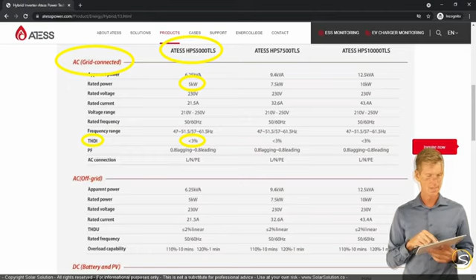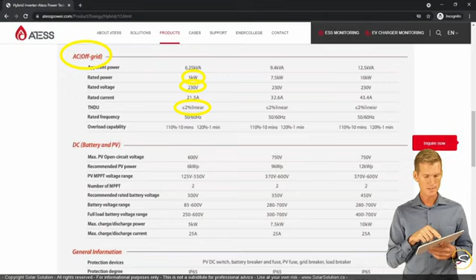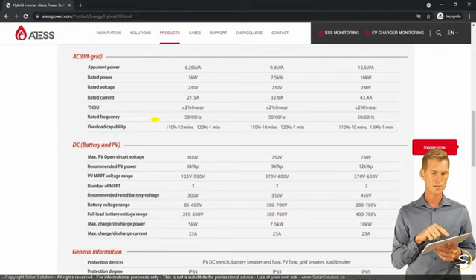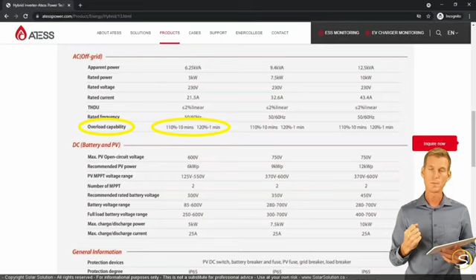And here in the second section you can see the values for when you're running off grid, so that's the connection between the hybrid inverter and you as the consumer of the power. And you can see that the rated power is equal to that for the grid connected. It's 230 volt of course as well. And the total harmonic distortion is less than 2%, which is pretty good. And you can see here that they indicate the peak power by means of the overload capability in percentages of the rated power. So you can draw 110% for 10 minutes or 120% for 1 minute, which makes a lot of sense. You can normally draw more than a nominal rated power from an inverter for a certain amount of time.